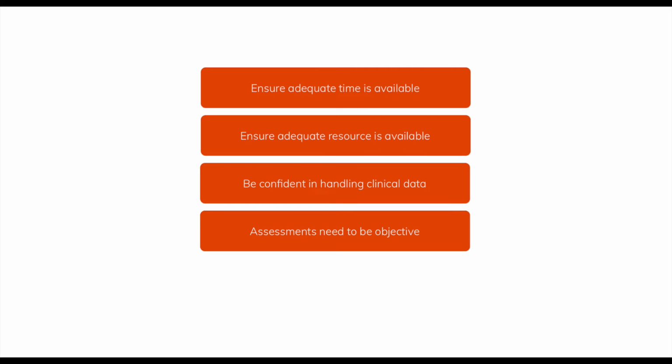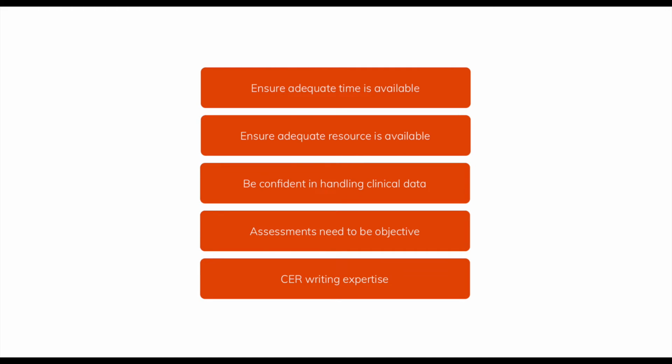Another requirement is that assessments of literature are objective. And so if you have someone involved in the CER who is directly part of the commercial team, then it could call into question the objectivity of the evaluation. So it's worth thinking about not just the skills of people involved, but also the roles and their responsibilities within the organisation. Something else you'll need access to is a level of medical writing expertise. Whoever takes overall responsibility for compiling the document needs to be confident in doing so and have an ability to write technical language while adhering to good principles of grammar.